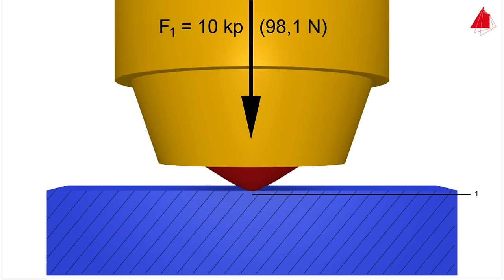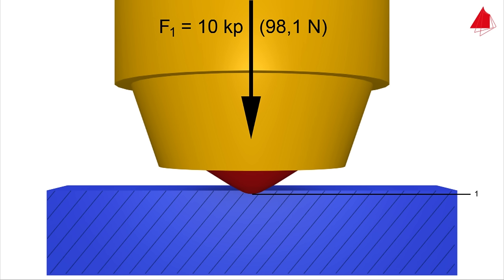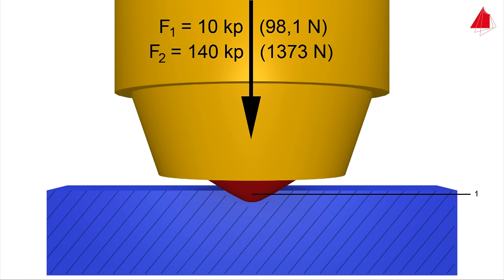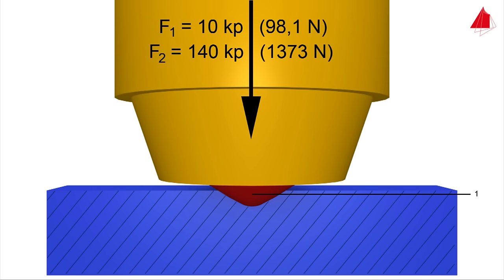In step 2, the test force is increased by 140 kiloponds which is acting as the major force. This means that an overall force of 150 kiloponds is now acting on the indenter and this force is held for a certain time.